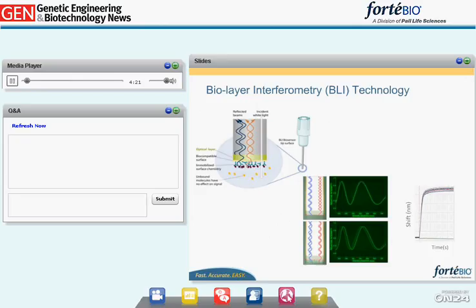The technology inside the Octet and Blitz systems is called biolayer interferometry, or BLI. This is an optical technique that utilizes white light passing through fiber optic cables into the biosensor. The white light bounces back to the detector at two distinct locations — one at a reference layer built just inside the tip of the biosensor, completely unaffected by the matrix, and the other reflecting from the tip where capture molecules meet the sample matrix. The two reflections undergo interference to produce an interference pattern monitored by the system.